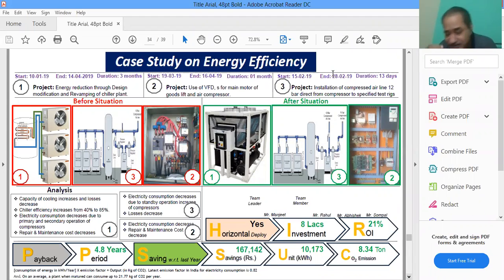We redesigned the chiller because we were using an indirect methodology - first chilling the water, which then went to the process plant for heat exchange. Instead of using water as a medium in our anodizing plant, where acid is used for plating, we took the acid out directly and chilled it through the chiller, doing away with water as the heat exchange medium. So our efficiency improved from 40% to 85%.